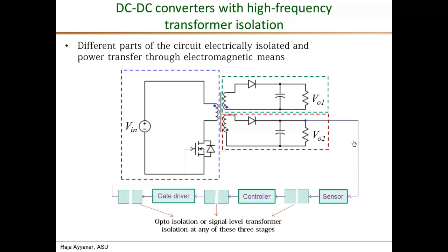Here is the output voltage that is sensed using the sensor, and either before it is passed to the controller, or from the controller to the gate drive, or within the gate drive itself, in any of these 3 stages we should have some form of electrical isolation. That could be through opto-isolation in these signals, or high frequency transformer-based isolation, again in the sensor or the controller, or very often it is realized in the gate drive itself using a pulse transformer for implementing the gate driver before it drives the gate of the MOSFET.